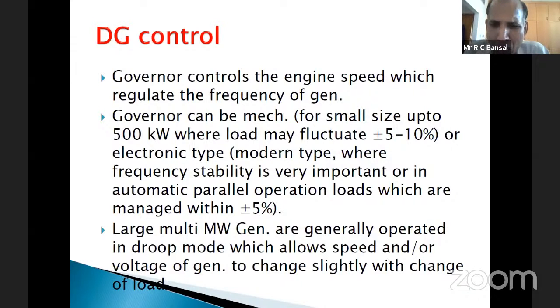The other control associated with the diesel generator is the voltage control, and that voltage control takes place in the synchronous generator connected on the same shaft of the diesel generator. So the excitation system will control the voltage, by changing the excitation current of the generator. So these two important controls are there.